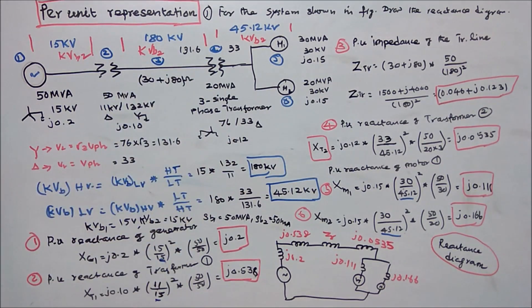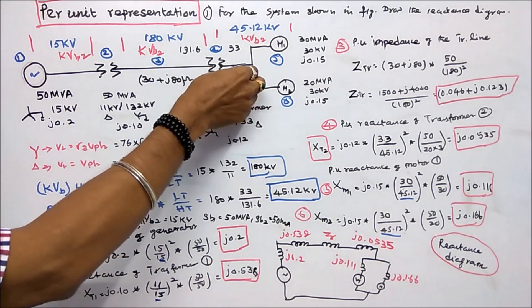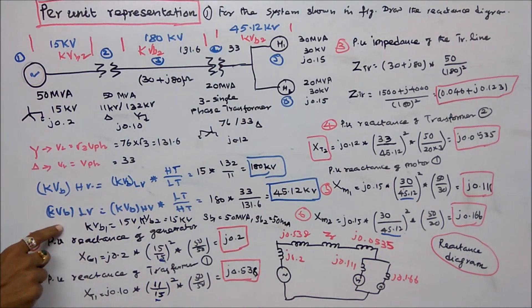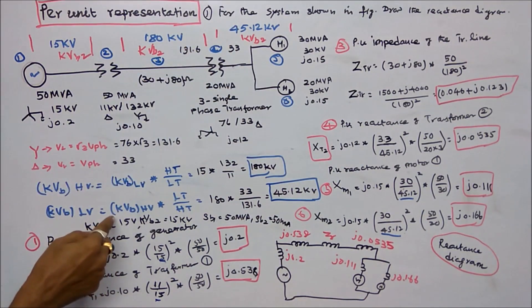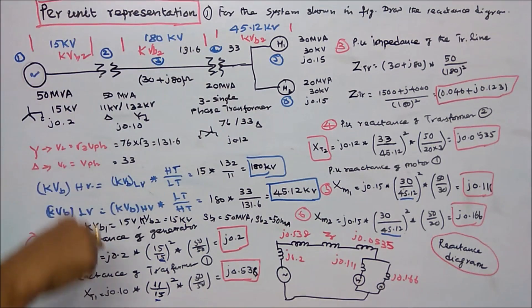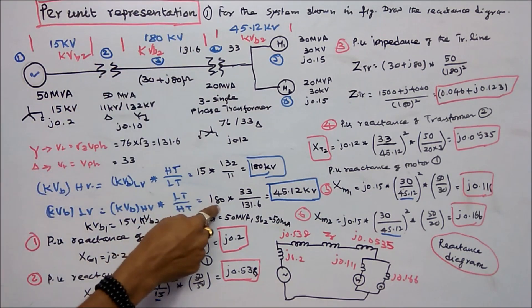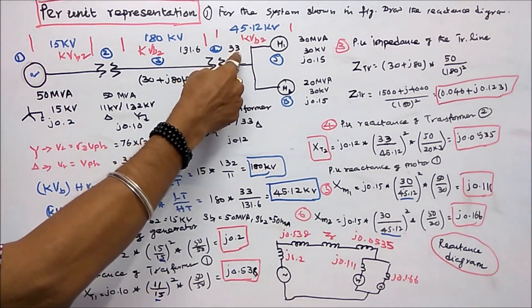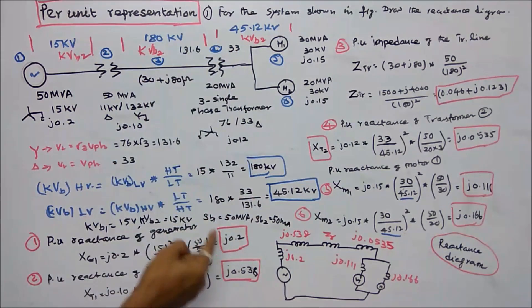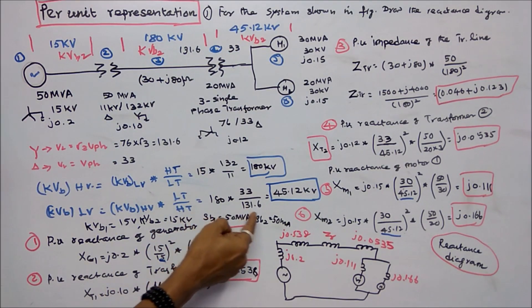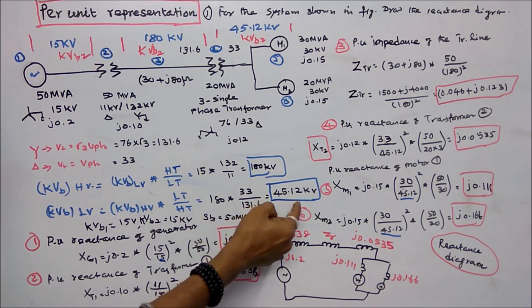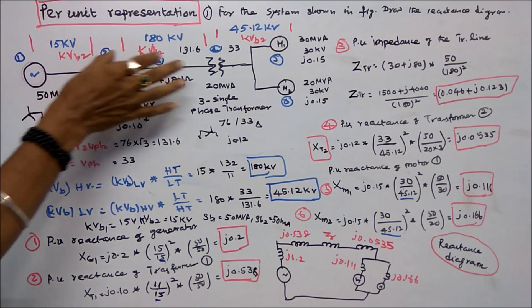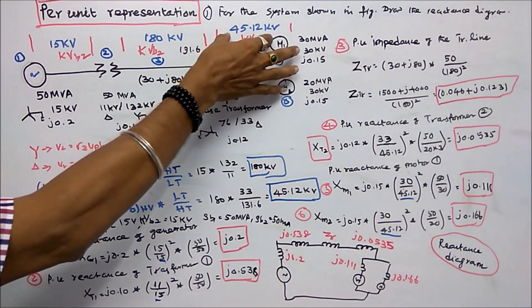Next, find the low voltage base on the motor side. Low voltage kV base equals high voltage base 180 into LT 33 divided by HT 131.6, giving 180 into 33/131.6, which equals 45.12 kV. So the base voltages are: 15 kV, 180 kV transmission side, and 45.12 kV on the motor side.